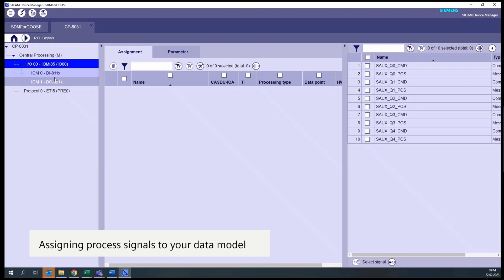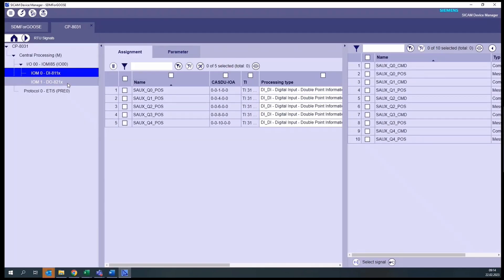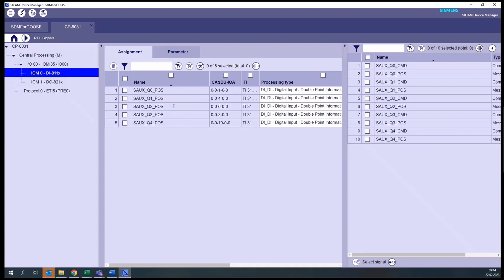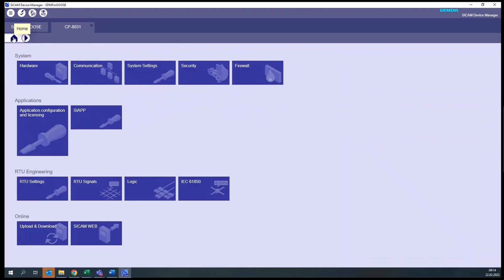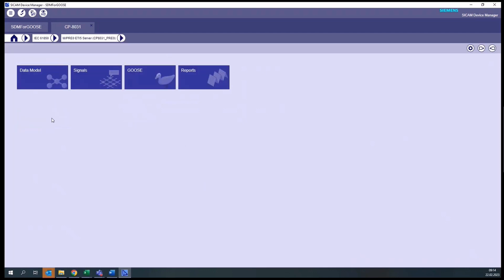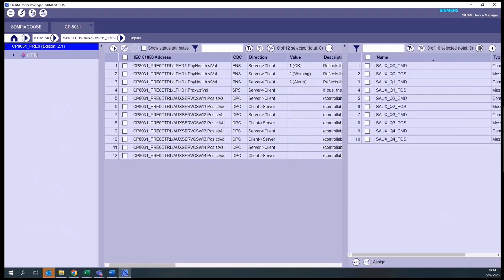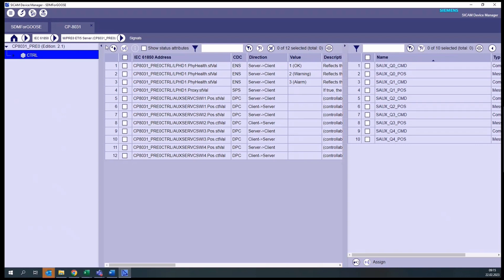The next step is to assign signals to the data model. In our RTU, we have already some signals coming from binary inputs and outputs. These signals would correspond to what we want to publish. In this example, we already have signals and commands for four circuit breakers, from Q0 to Q3. To assign these signals to the data model, we go to Home, then click on IEC 61850 Server, and then on Signals. If we select the IED name, we will see all the elements in the data model, or if we select the logical device, we will see just the elements assigned to it.